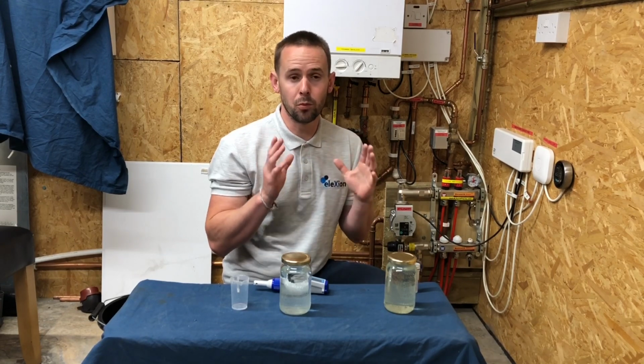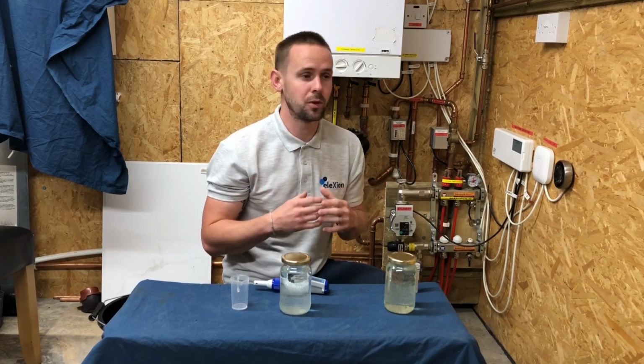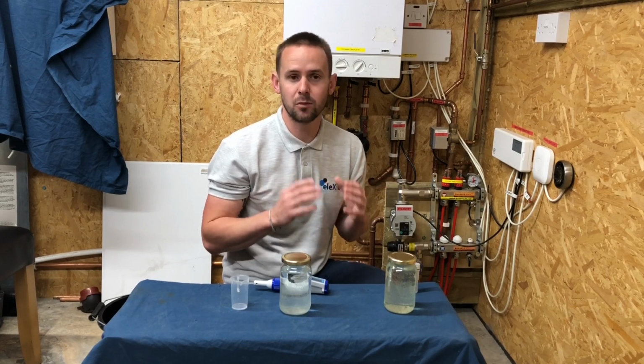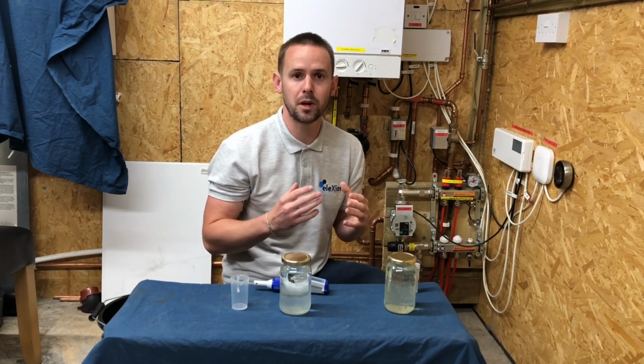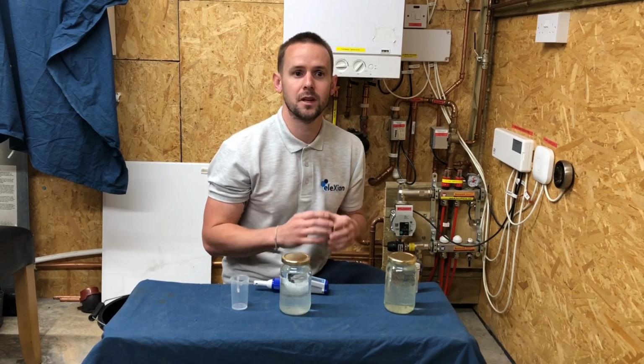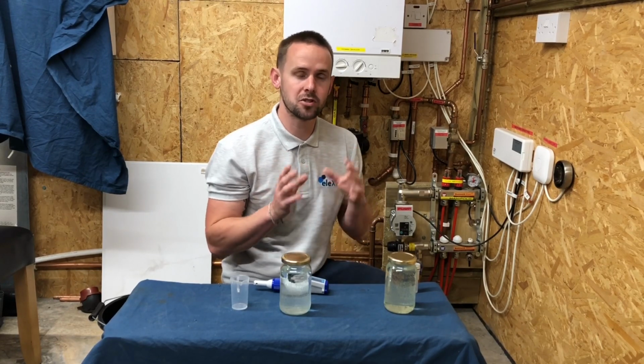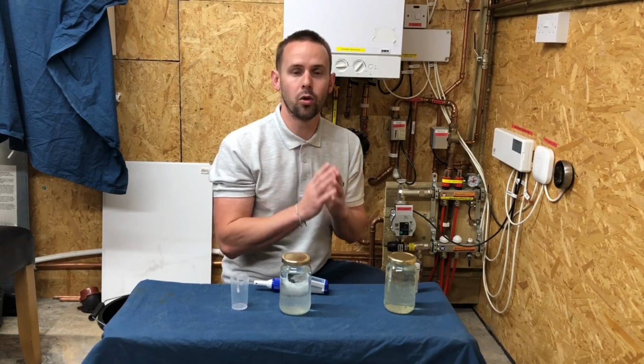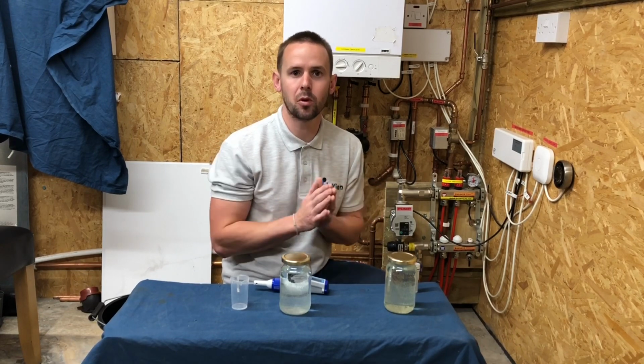What this stresses is that when we're cleaning the systems, we need to make sure that any chemicals we use, we really do flush out properly, and we check it as we're doing it. So we know once we start to treat the system that all the residue's gone and we're going to get the results that we require.